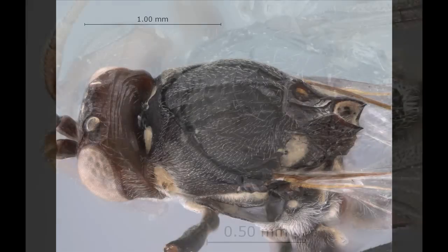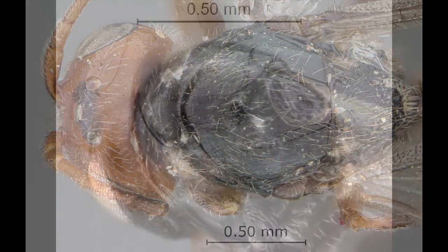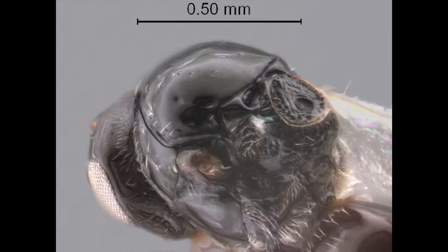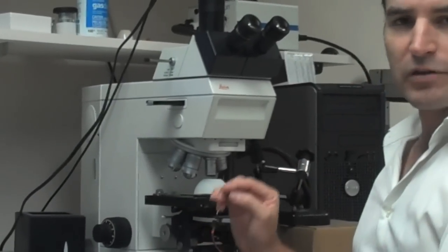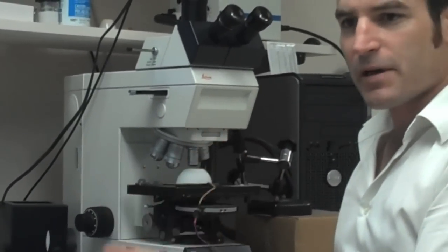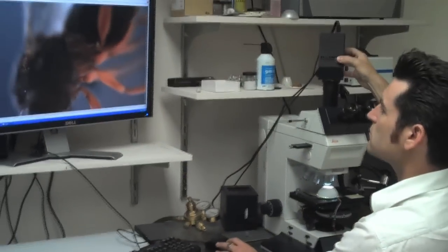The two major factors involved in the success of this system: the first being the type of lenses. The objective lenses we use are what are known as metallurgical grade objective lenses.